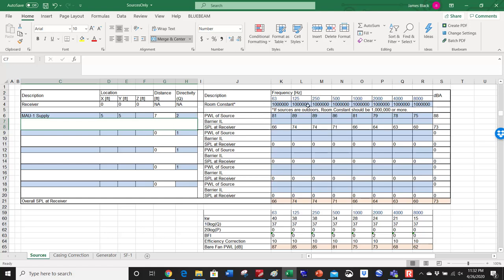So over here, I have the room constant. In this particular case, it's, say, a makeup air unit. Say you have a project where none of the air can be reused. Maybe I shouldn't say that none of the air can be used, but in a kitchen, you have these exhaust fans, and they're separate from the system. You have all the hoods over all the stoves and all that stuff. All that air just needs to be exhausted out and not brought back into the building. So you need to have a unit that just brings in makeup air, just supply air.